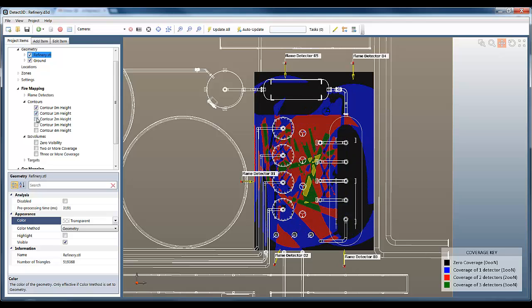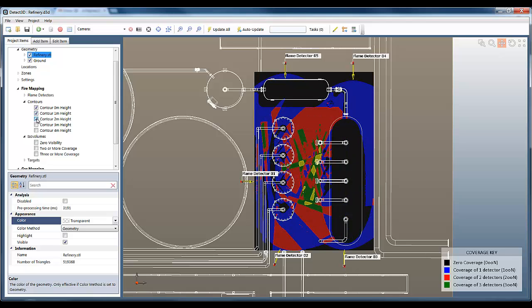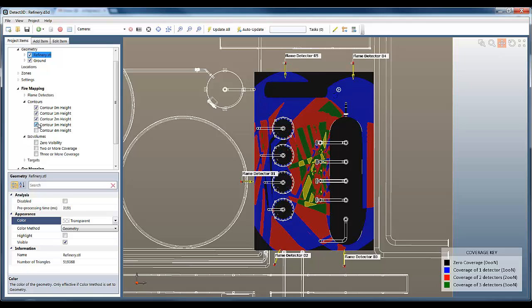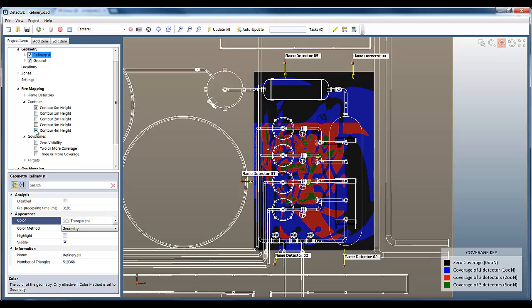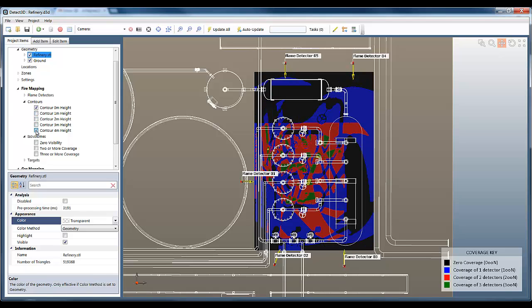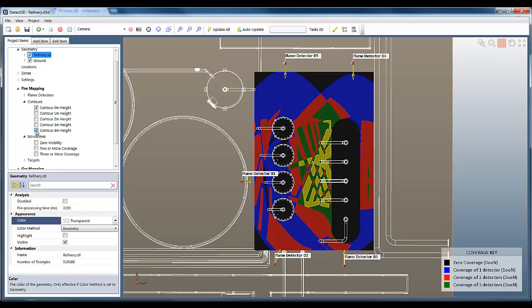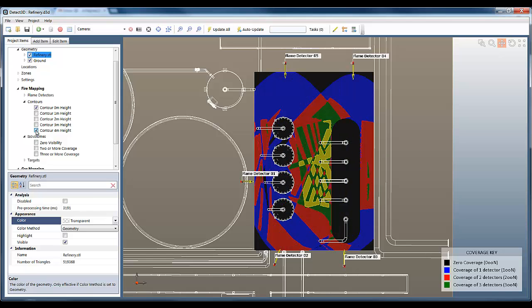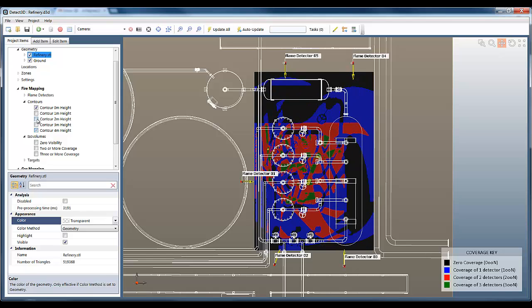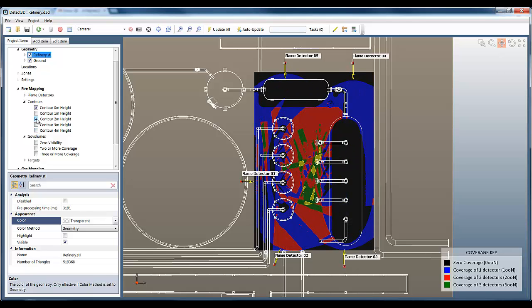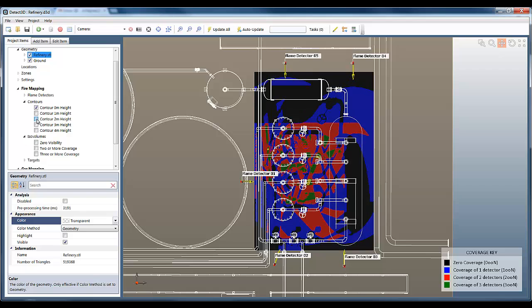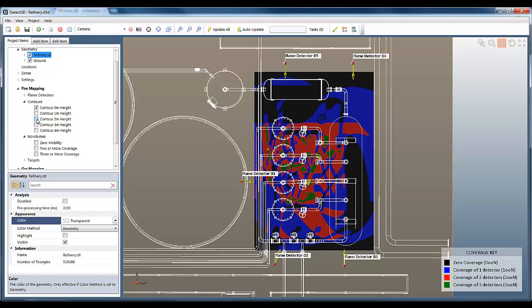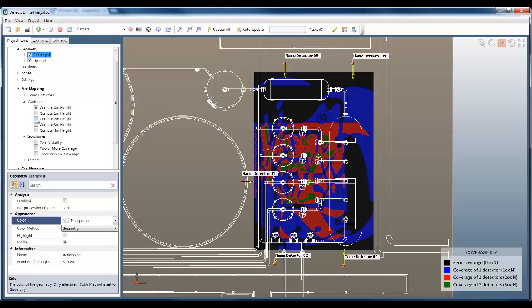I can cycle through these contours at 1, 2, 3, and 4 meters height. The critical point here is that the coverage is different at each height. The colors dramatically change, and not only does it look different, but if you calculate the coverage for each of these 2D fire zones by area, you can see that the coverage itself changes with height.